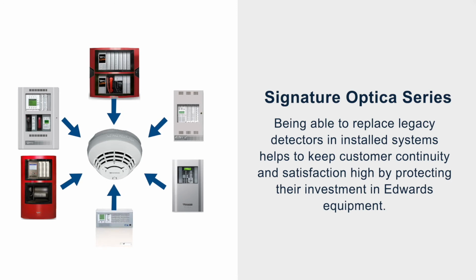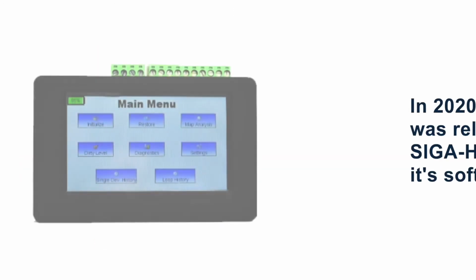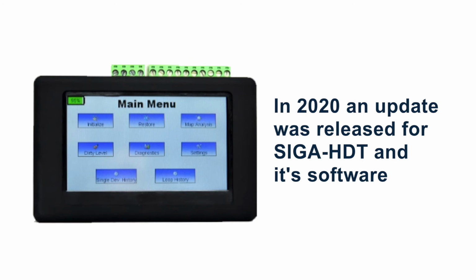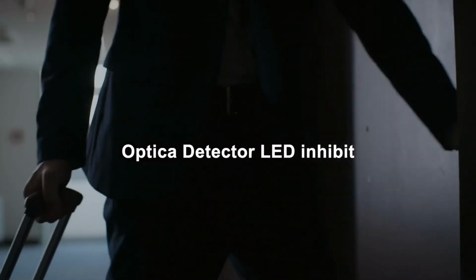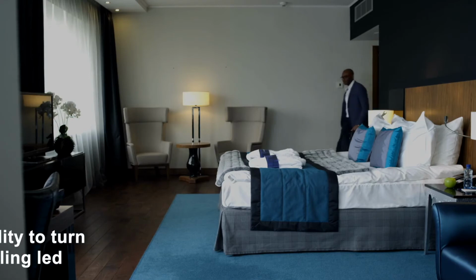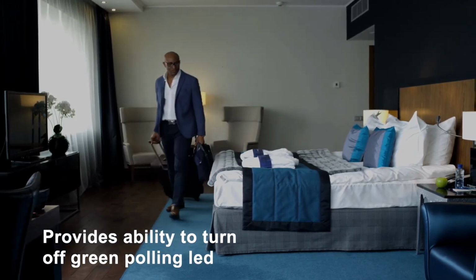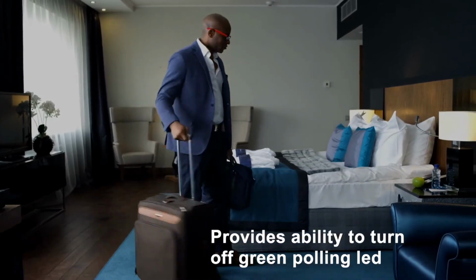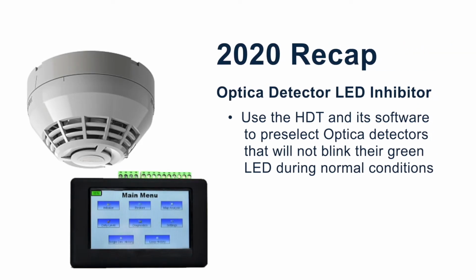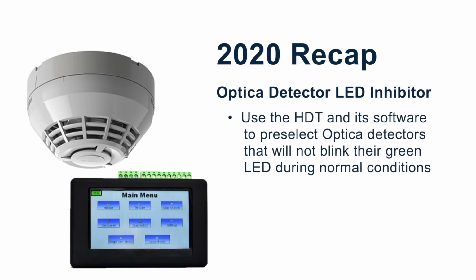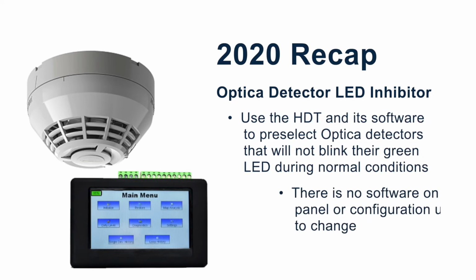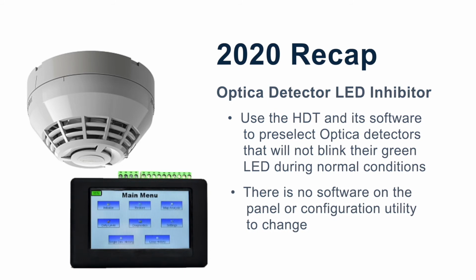On top of these unique capabilities, being able to replace legacy detectors in installed systems really helps to keep customer continuity and satisfaction high by protecting their investment in Edwards equipment. In 2020, we also saw the release of the SIGA HDT and its software. In this update, we added the capability for those hotel or bedroom applications who want to offer guests a totally dark experience with no background flashing lights. You can use the HDT and its software to pre-select Optica detectors that will not blink their green LED during normal operations. There's no software on the panel or configuration utility to change.